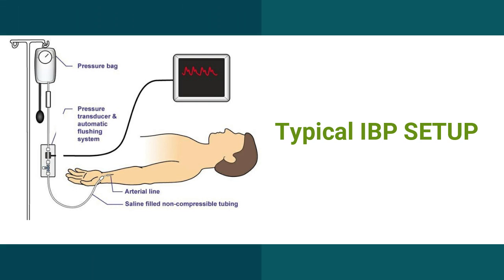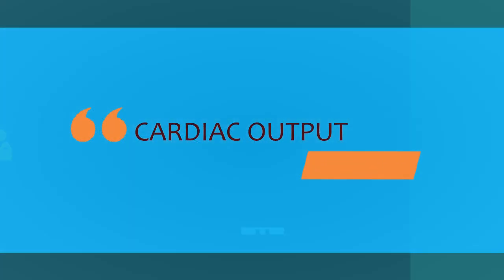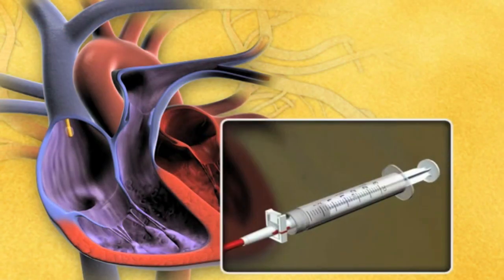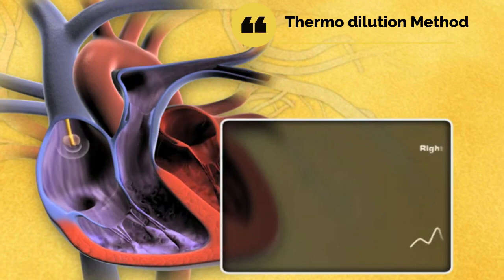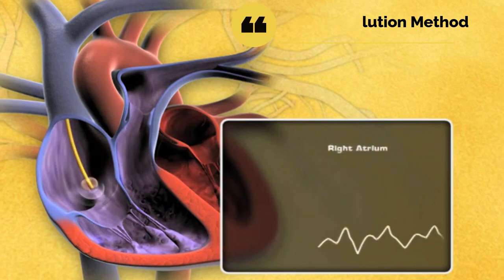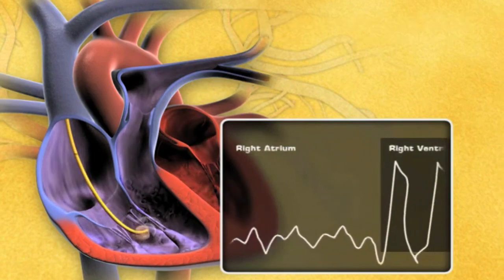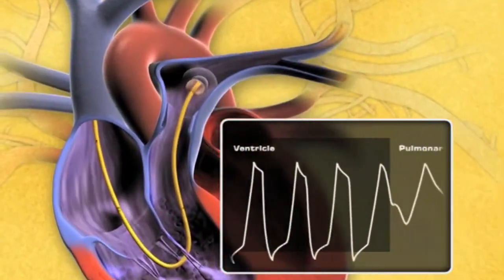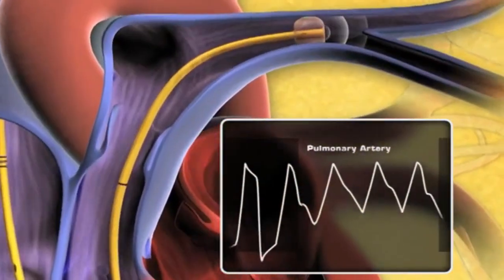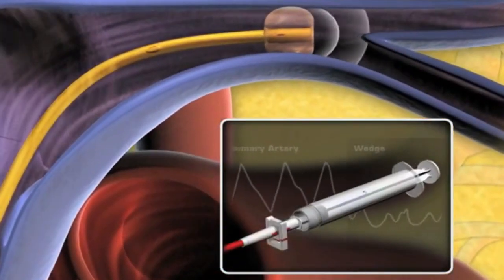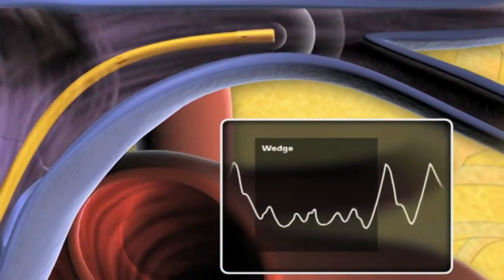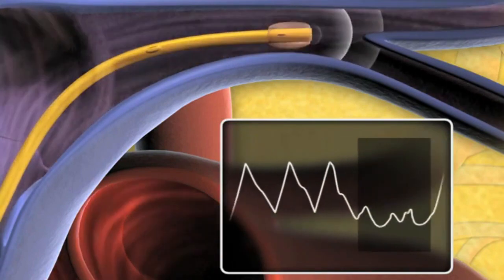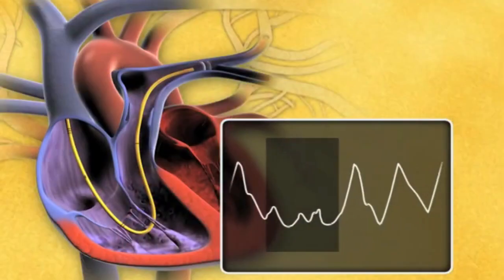Let's advance towards cardiac output monitoring. The direct method of pressure measurement is used when the highest degree of absolute accuracy, dynamic response, and continuous monitoring is required. This method is also used to measure the pressure in deep regions inaccessible by indirect means. For direct measurement, a catheter or needle-type probe is inserted through a vein or artery to the area of interest.